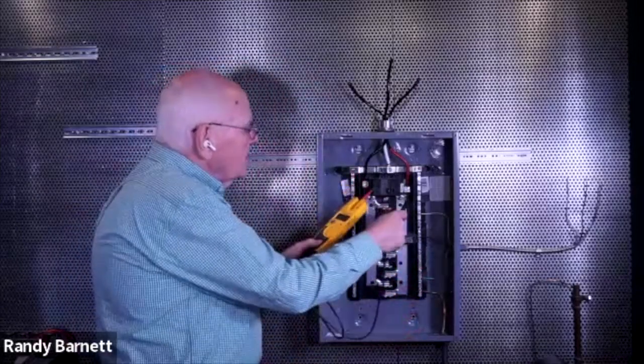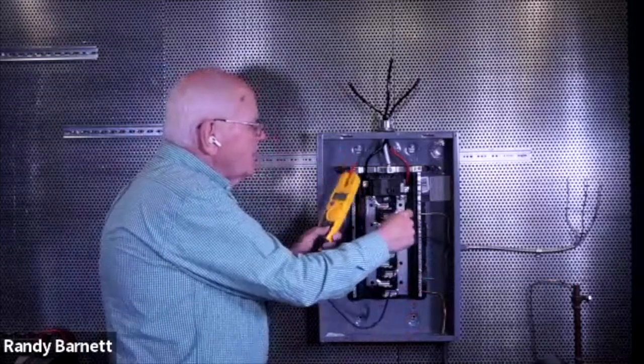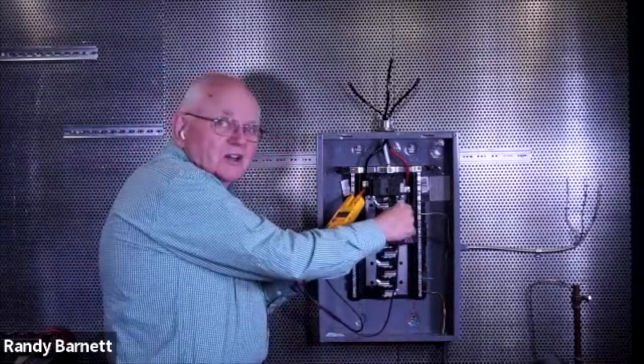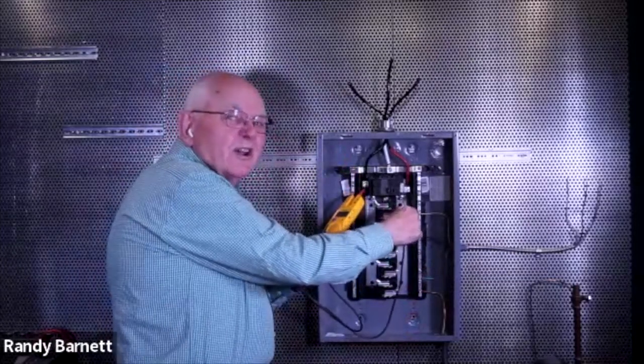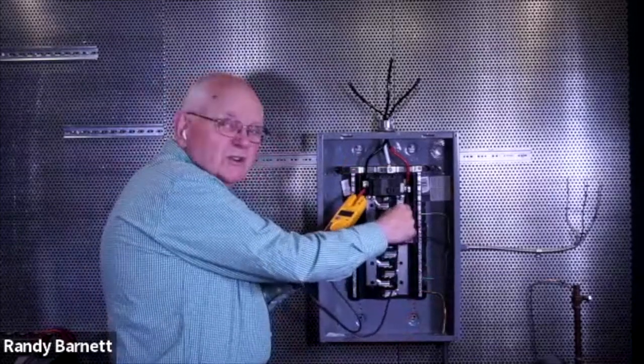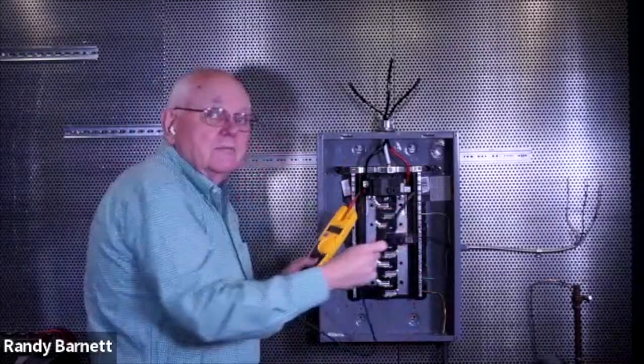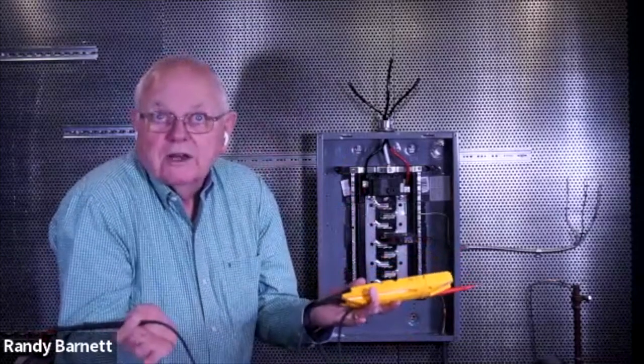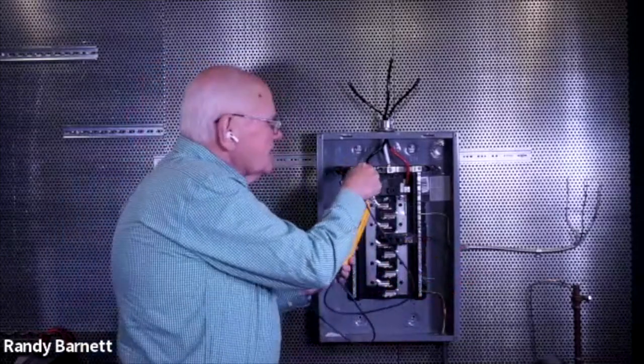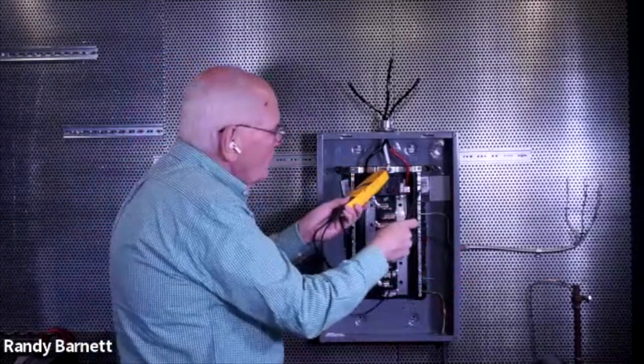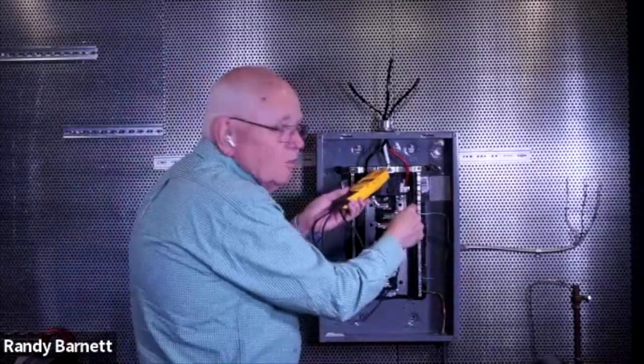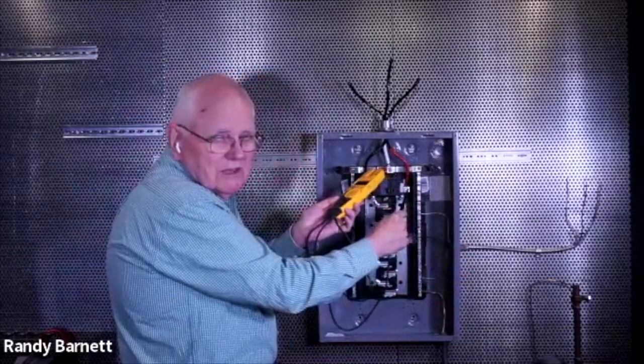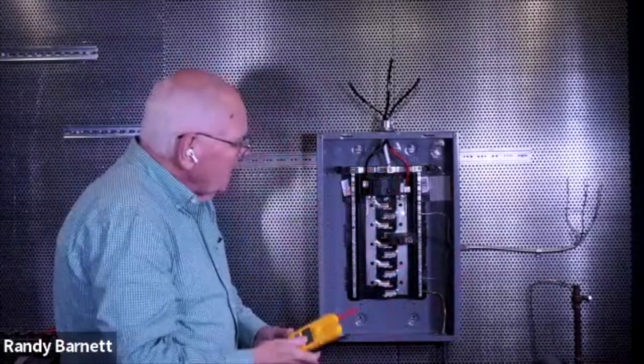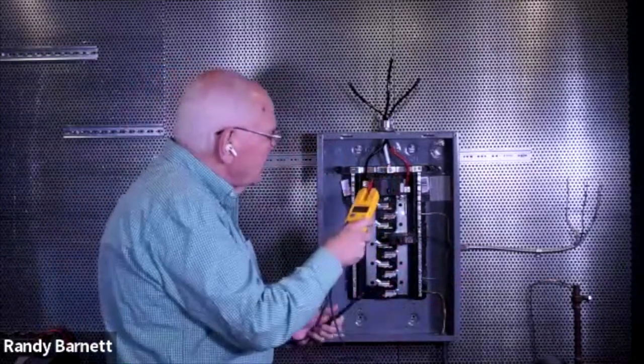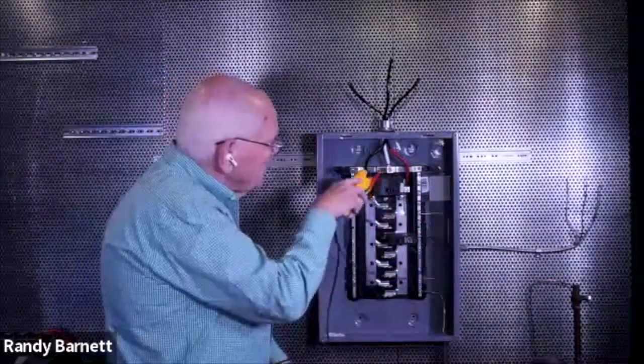So if I read from the black, the ungrounded black conductor, to the ungrounded red conductor, I'd get 240 volts on my meter. The midpoint of 240 is 120, right? So if I read from the black to the white, I get 120. Or if I read from the red to the white, I would get 120 on my meter. Now, that makes sense then if I take a conductor, and actually you can see there's a bus bar.